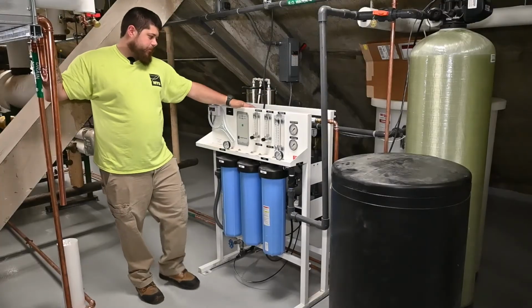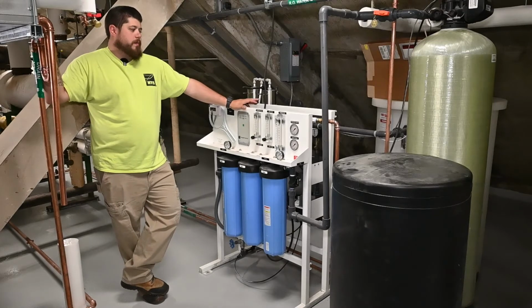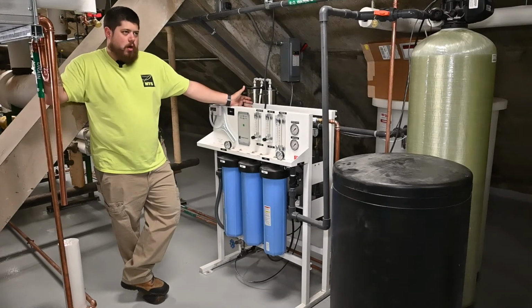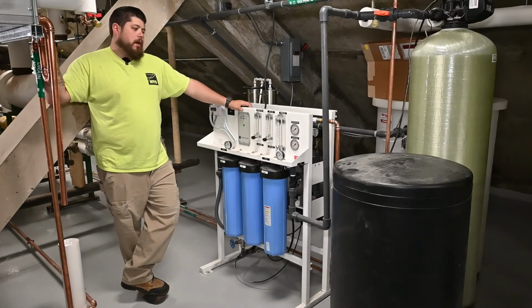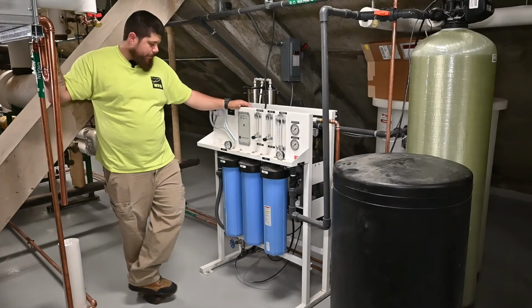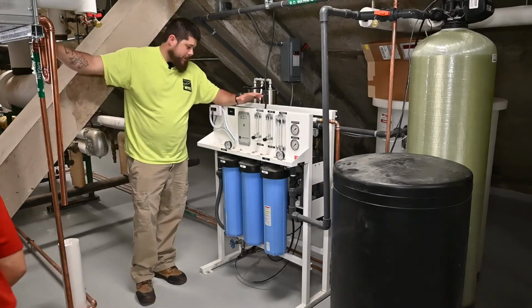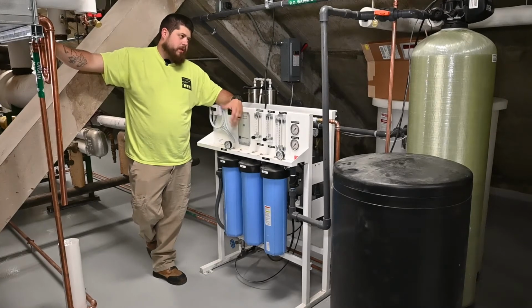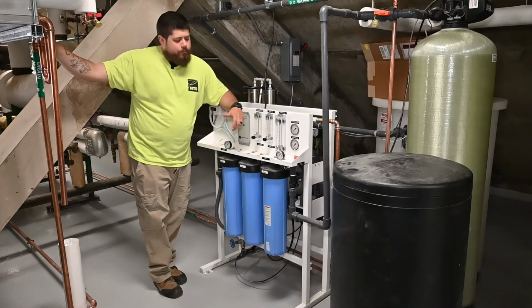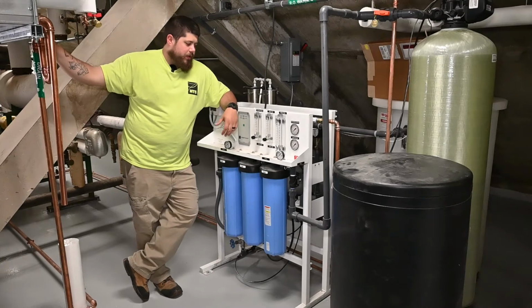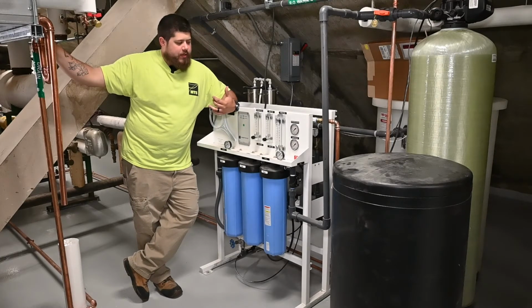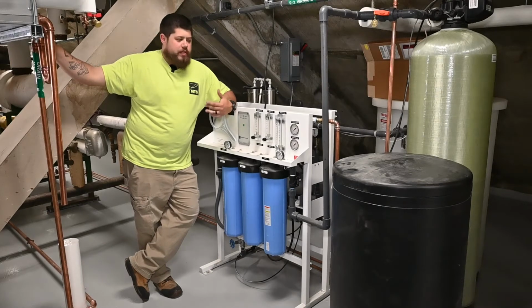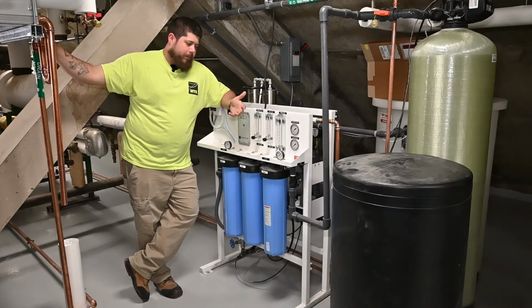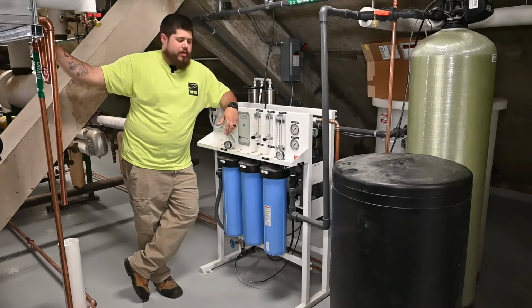So, this is a Neptronic RO skid. This skid feeds all of the 7 humidifiers up in this mechanical room. The maintenance that needs to get done is primarily these 3 filters and adding salt to the system. I mentioned earlier that the recommendation for changing these filters is based off of run time. If it's in the winter and it's running on and off for 2 months, my recommendation would be to change these filters.